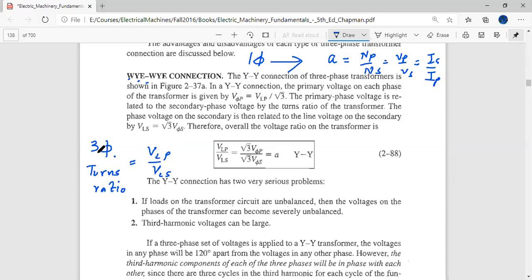So for a three phase transformer, the definition of A is standard. It is equal to Vp over Vs, which was defined for a single phase. This was defined for a phase ratio - this is not the line voltage, because this is a one phase transformer. So A is always defined as the phase voltage ratio, V primary voltage per phase, secondary voltage per phase.